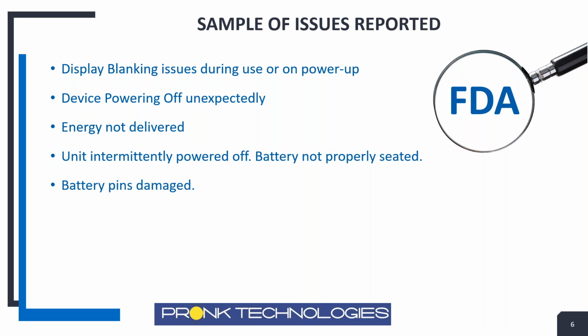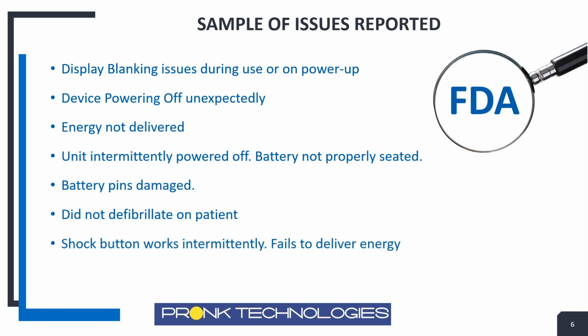Battery pins damaged. So of course batteries are a common thing that you have to check and replace on defibs, and it was interesting to me how many incidents were reported about the battery pins being damaged, which can of course cause an intermittent contact. So that brought to light some defibrillator designs. They have a lot of contacts on their defib battery contacts, and they can be deformed in some way where the battery's not making good contact. So you don't want to always assume that when you power it up once, it's going to work. You want to inspect these things to make sure that there's no physical damage to them.